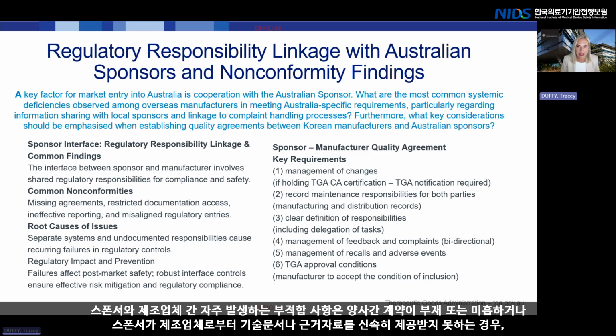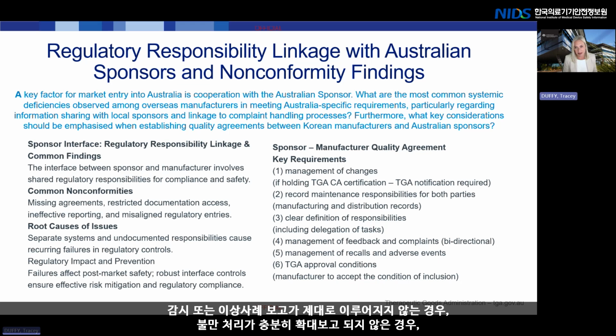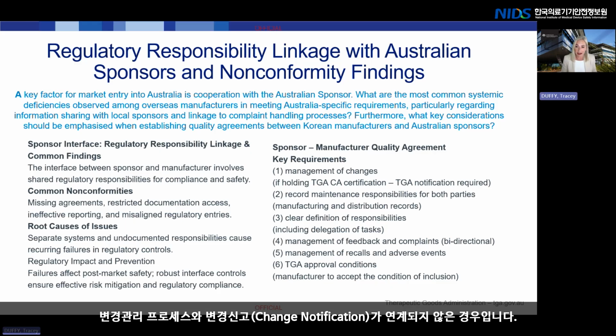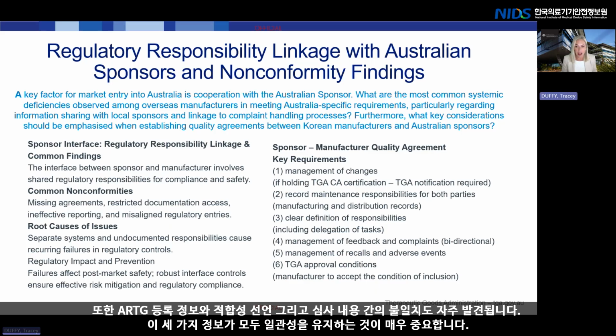In terms of common sponsor interface non-conformities, we regularly have missing or incomplete agreements between sponsors and manufacturers. The sponsors might not be able to access technical documentation from the manufacturer or provide evidence promptly. There's sometimes ineffective vigilance or adverse event reporting. There's sometimes weak complaint escalation processes, including between the sponsor and the manufacturer. Change notifications are an area that may not be integrated into the change control processes. And what we are also seeing is the misalignment between the information about the device on our register, the declaration of conformity, and what's looked at in the audit. So making sure that there's consistency between all those three things are really important things.